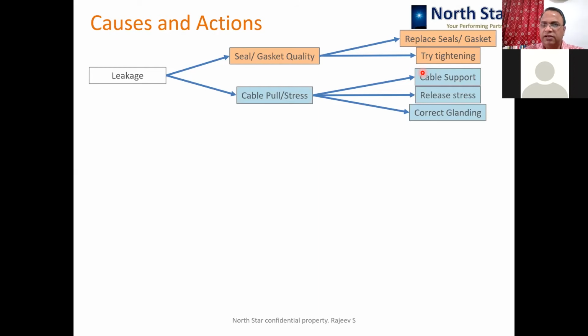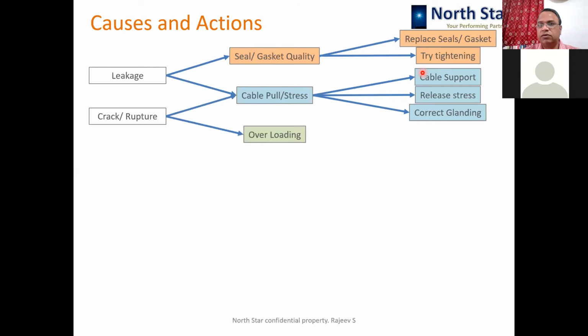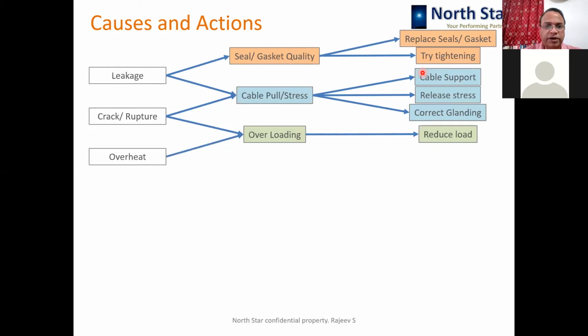Okay, glanding sometimes we also found is not right. The gland is not holding the cable, and the cable is freely moving in the gland, and because of that all the weight of the cable comes on the bushing, and it causes leakage. For cracking and rupture, again cable pull stress is the reason, and overloading also causes failure and cracking of the bushing. So of course the load is to be moderated.